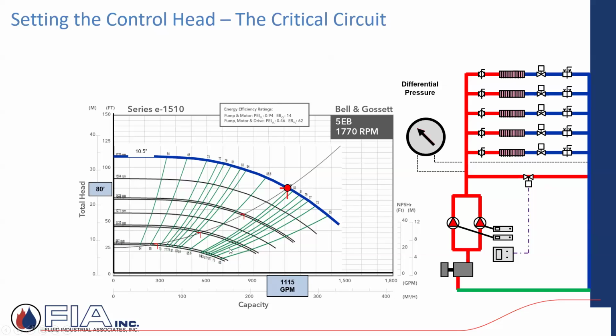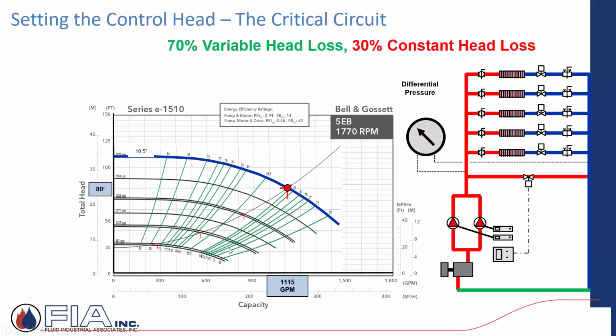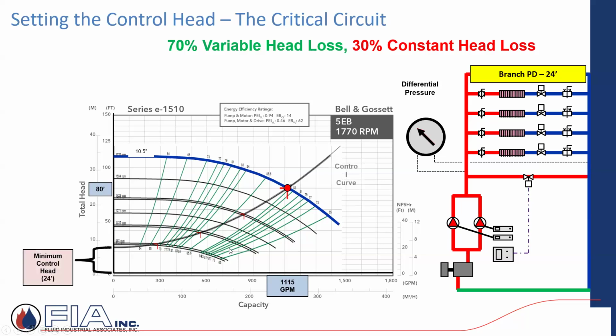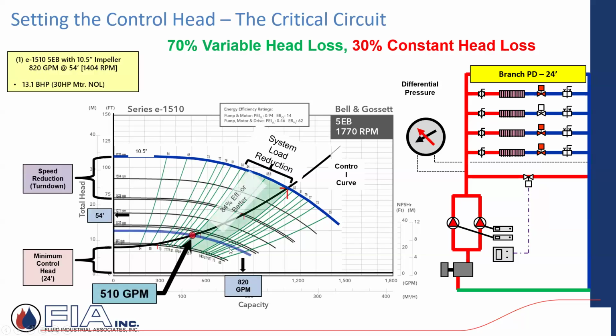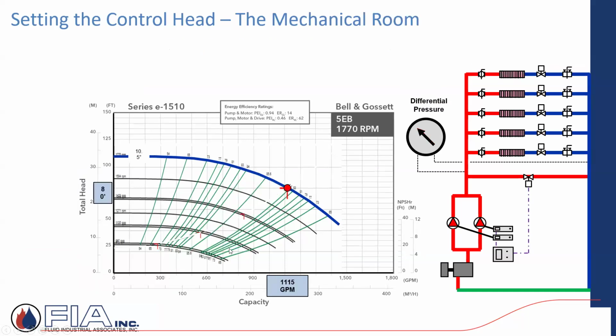In this case here, we're saying 1115, again, 1115 GPM, 80 feet of head. In this case, we have variable percentage of 70% and a constant of 30, right? And that's at 54. So here's my range in terms of dropping from 1115 down to 510, and efficiencies are still maintained. Here's my speed reduction, my turn down. But I still have to maintain that minimum. I got to maintain that control head of 24 feet of head.